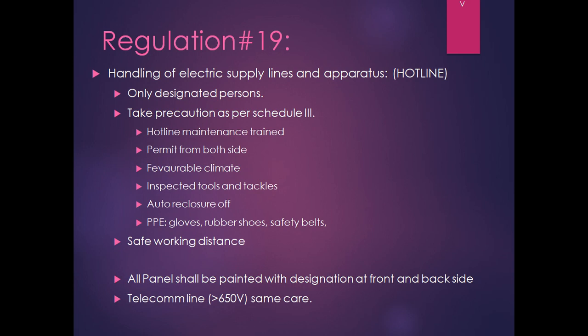We'll see this. All panels should be painted with designation at front as well as at back side. So this is required. Earlier many people used to write the panel designation on the front side only, but it may have some problem. Suppose there are 3 panels, you need to operate on the panel number 1, which is at your left hand side from the front side. You isolated the panel from front side. Now you go to the back side.